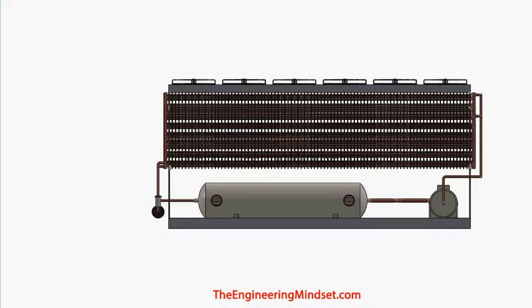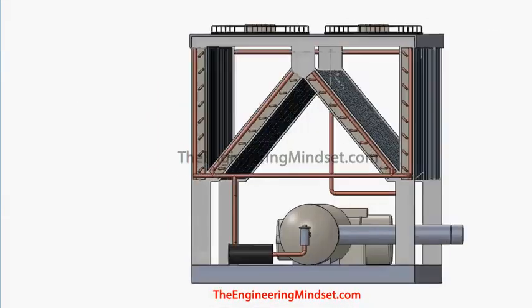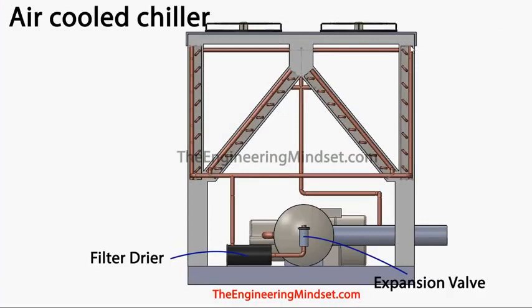So if we change the view again on this one, you can see on this end all the refrigerant will then collect up after it's cooled down in the condenser, and it will then flow into these headers and make its way down into the filter dryer. That will then pass through there and make its way off and up into the expansion valve. So again, by the time the refrigerant makes its way to the expansion valve, it should now be a high pressure, medium temperature, saturated liquid.